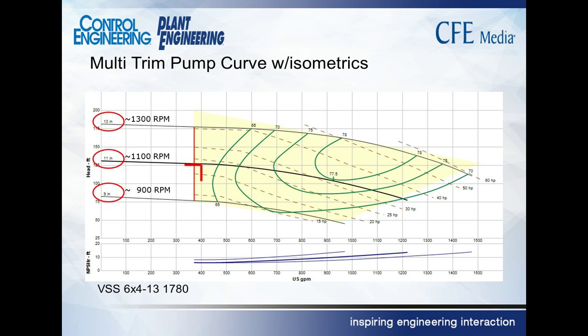That might be another topic for discussion. Stumbling blocks when changing speed. A lot of those have to do with the particular method that you use to change the speed. That was a gotcha for variable frequency drives. Are there gotchas for going to DC motors? Sure. How about going to gasoline engines? You bet. There's all kinds of problems you get into. As far as the pump itself, the pump really doesn't care much. There's no real bad gotchas that I can think of off the top of my head. Most of them have to do with whatever you're using to vary the speed.